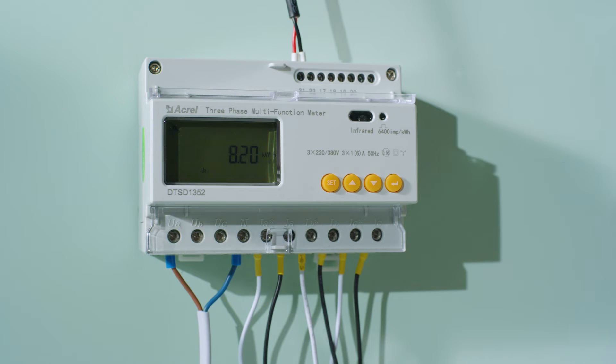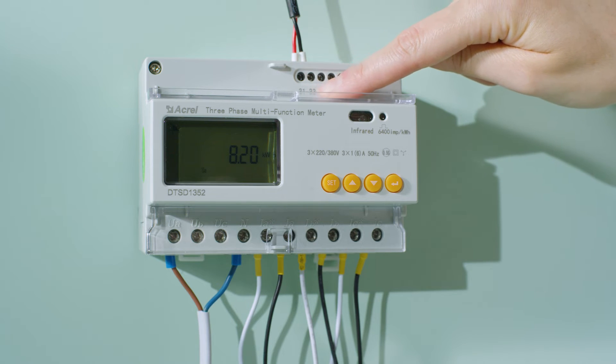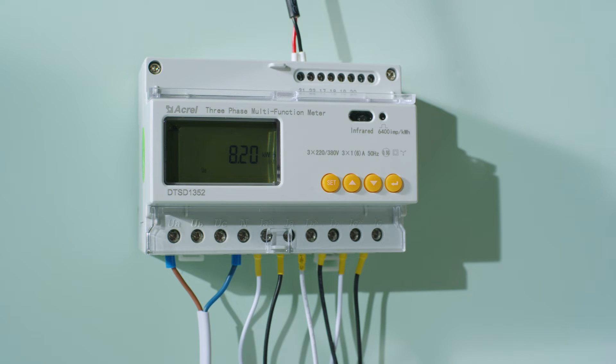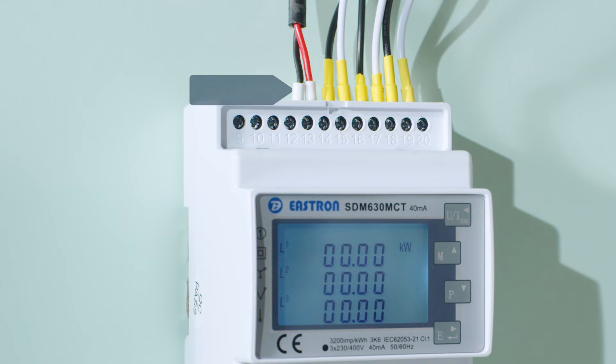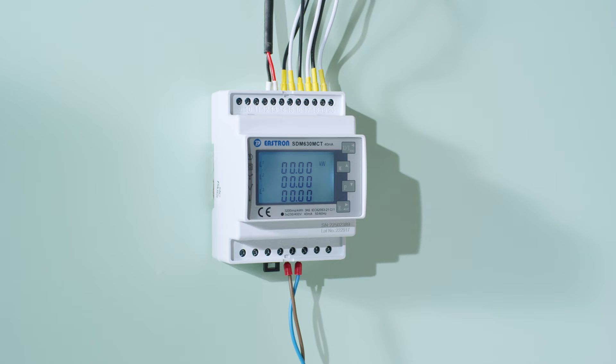Connect the RS485 wires. For Acuvim meters, use connection points 21 and 22. For Eastron meters, use connection points 13 and 14. Please note that the direction of the phase numbering is opposite compared to Acuvim meters.